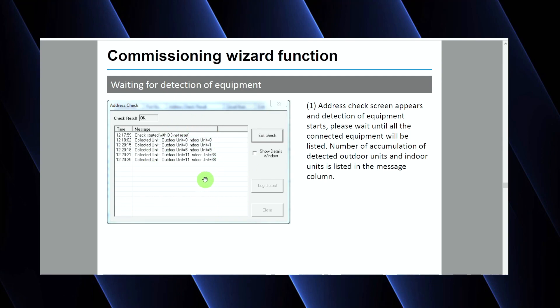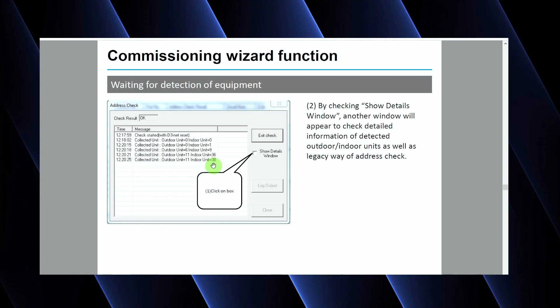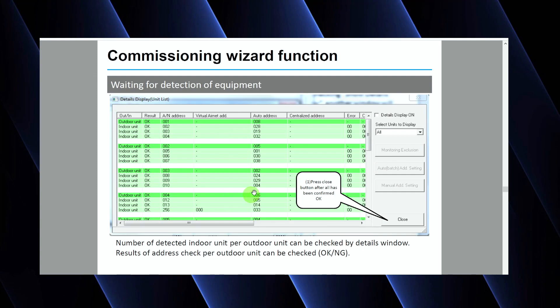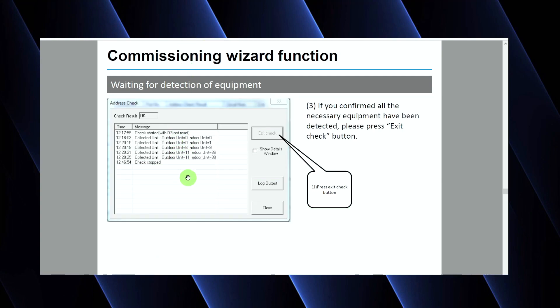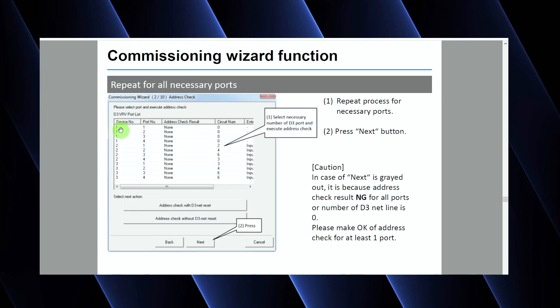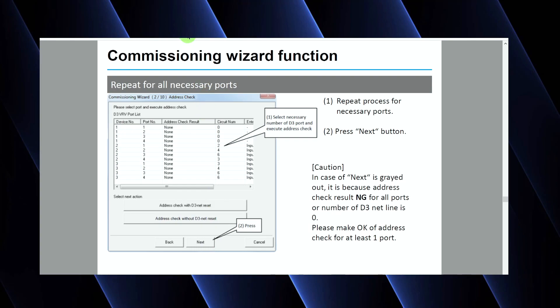It should go ahead and start this window, which is checking for the equipment. This will take some time — you need to be patient. It's going to start the check and then start collecting all of the data. In this particular case, we had 11 outdoor units with 38 indoor units on the system. Wait for it to complete before you click any buttons on the right-hand side. If you want to see more information about what the unit has seen, you can click the 'Show Details' window and it's basically going to show you all of the data that it has seen so far. Go ahead and click 'Close' to go back to the previous screen. Once the check is complete, you can exit the check and close out of this window. If you have any other ports to check, do that now and repeat the process. Once you're all done, click 'Next' to go to the next step of the wizard.